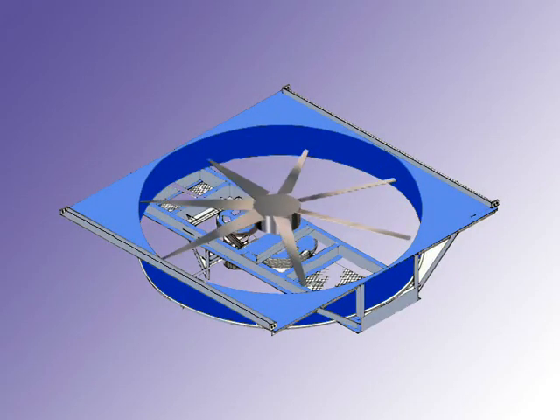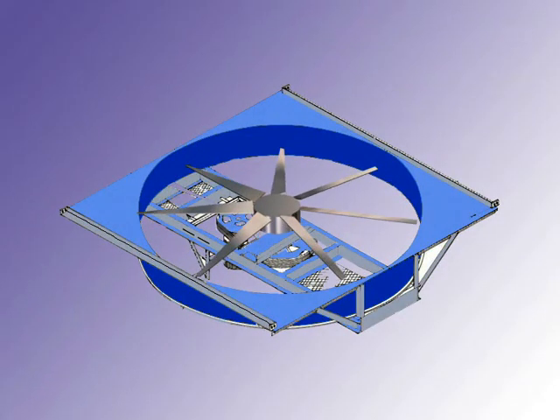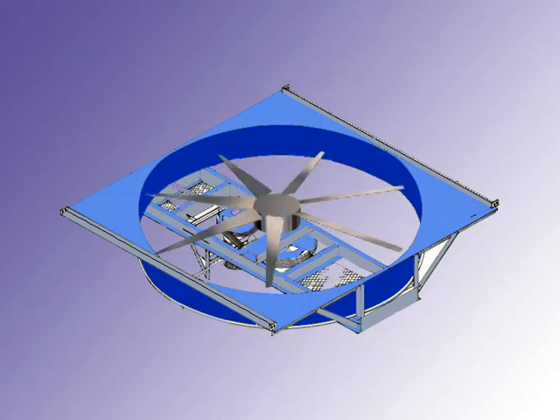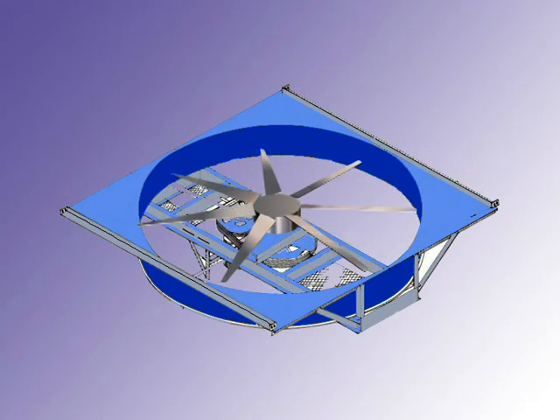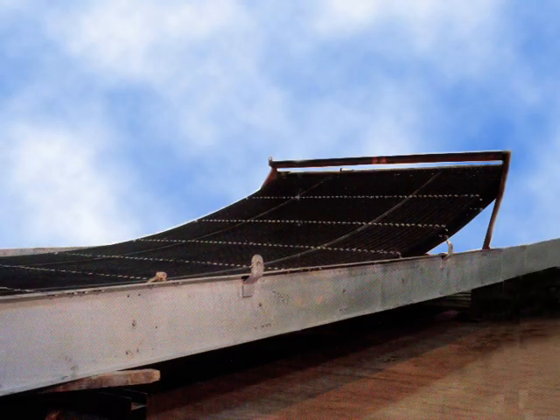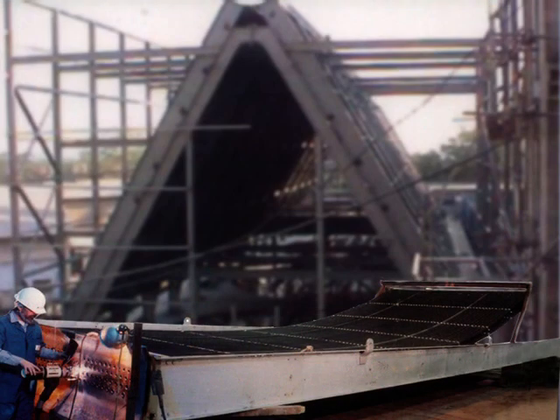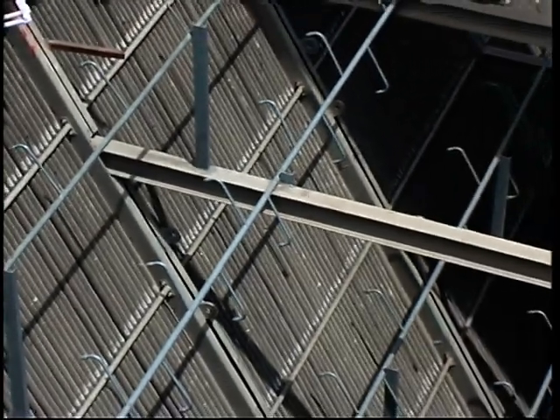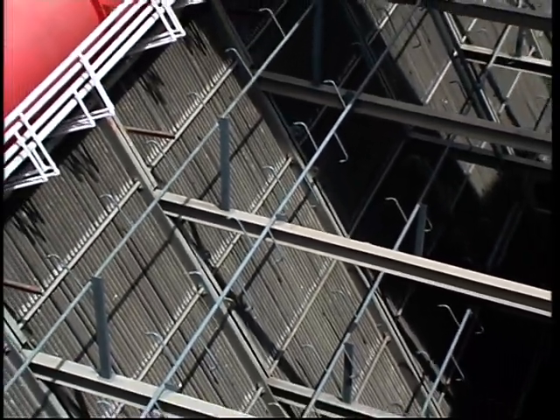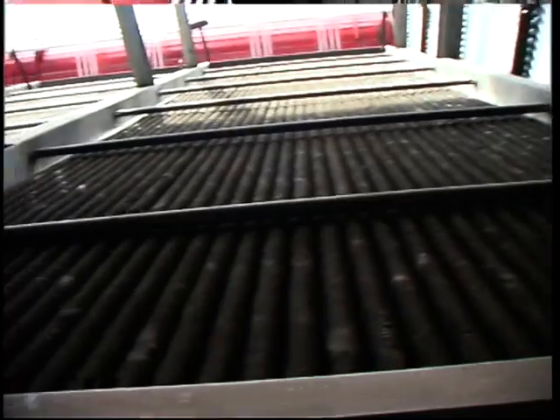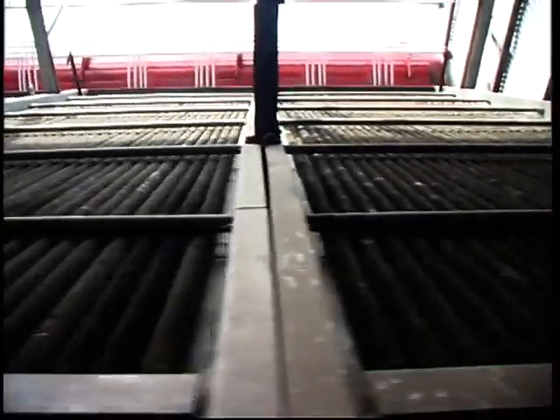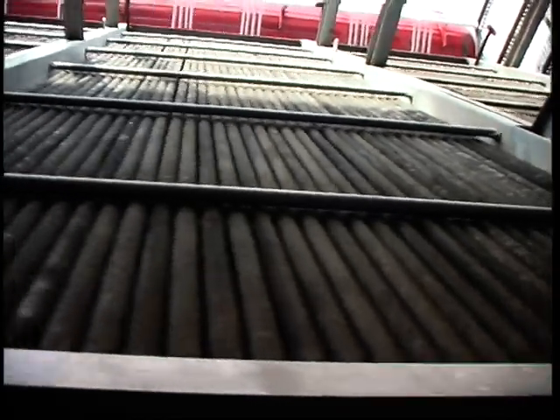2. It offers the flexibility to handle off-design conditions at partial load, something which is not possible in dephlegmator type of configuration. 3. As the rear headers can be lifted mechanically without dismantling the bundle, any leaking tube-to-tubesheet joint can be easily identified and repaired. 4. Progressive thermal expansion can be accommodated in the tube layout pattern. 5. Unequal condensation in tube rows across the bundles is compensated by varying the finned tube diameter.